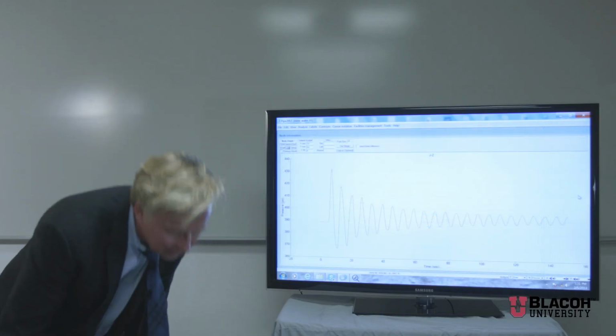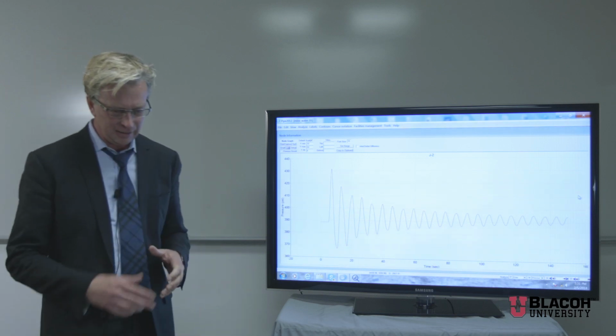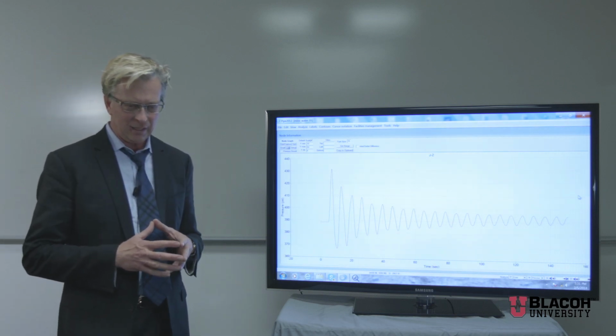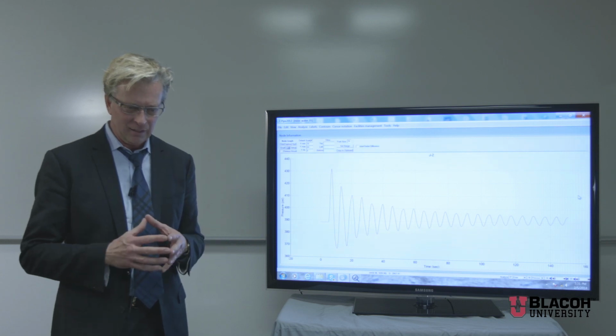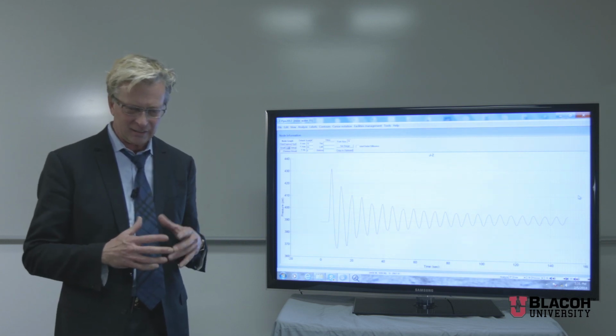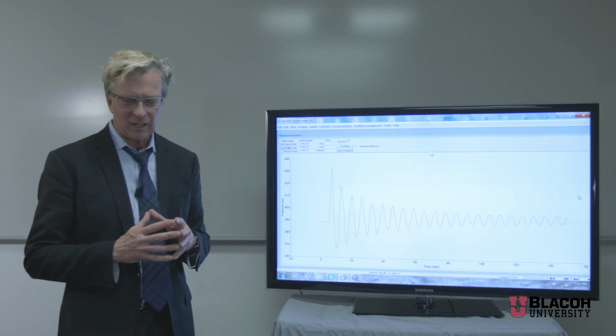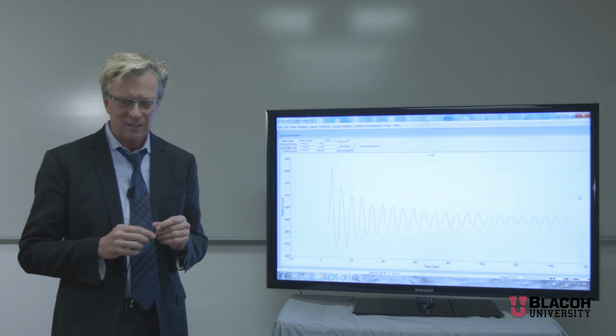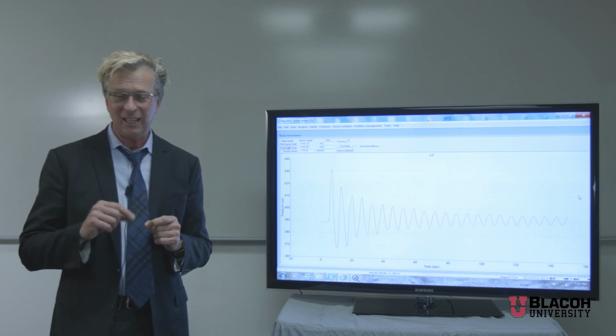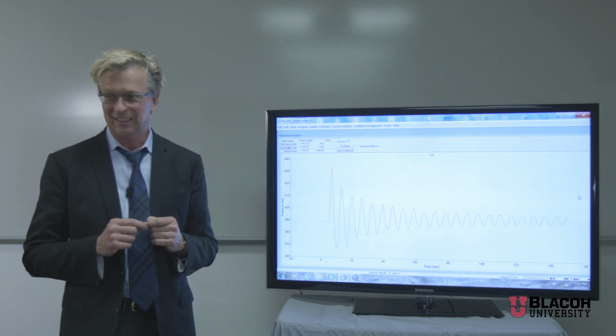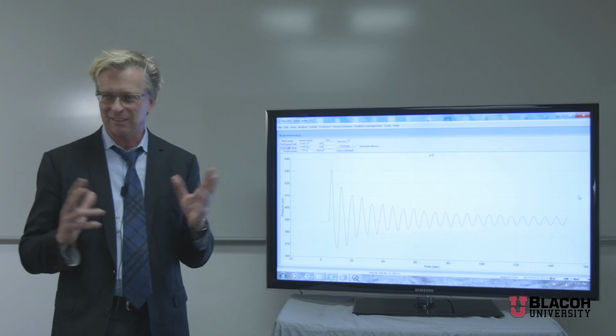So just to give you an example, this would be on the upstream side, looking at the pressure, giving and receiving energy. And as you can see, it's still got a good rock and roll. In this case, to date, they have not put in a surge vessel yet. I guess they're waiting for the whole piping to come loose and fall down 5,000 feet into the earth. When it's on World News Tonight, you're like, geez, that's that nickel mine in Canada that they're having problems with, right?